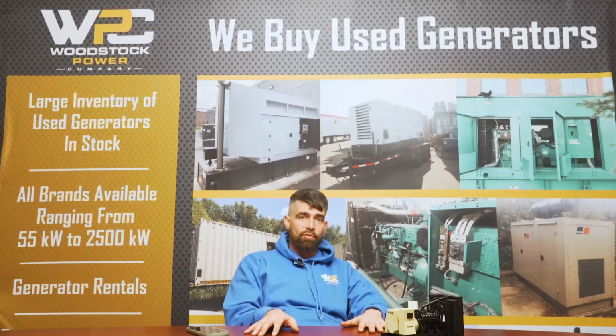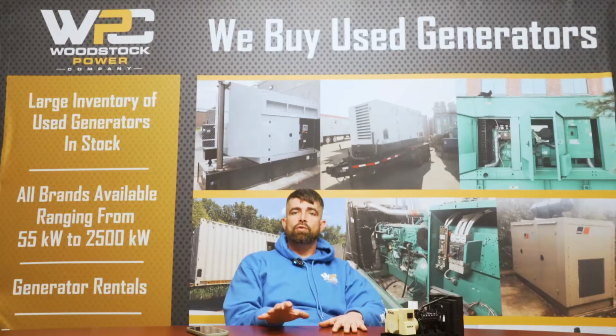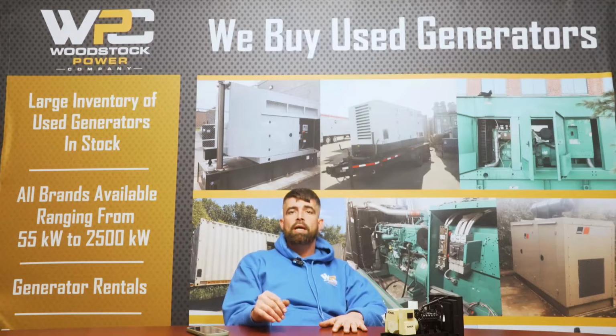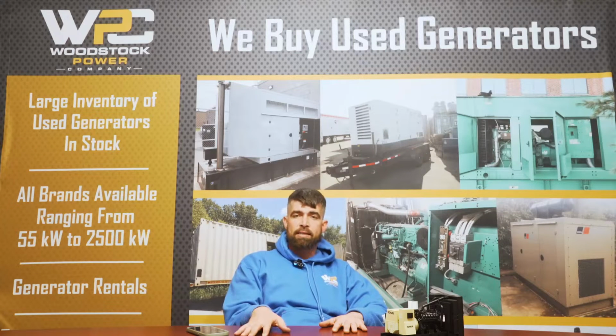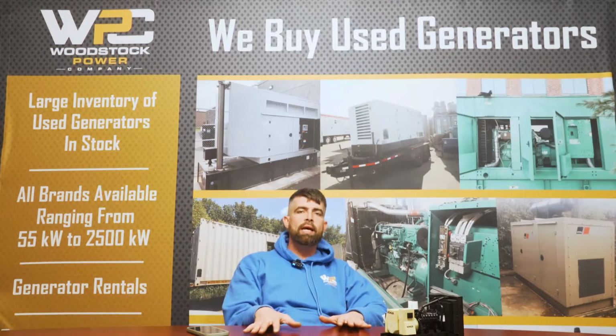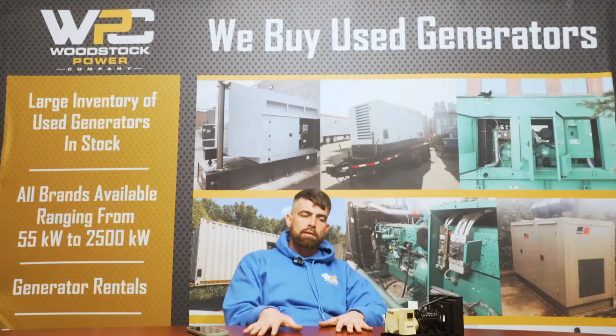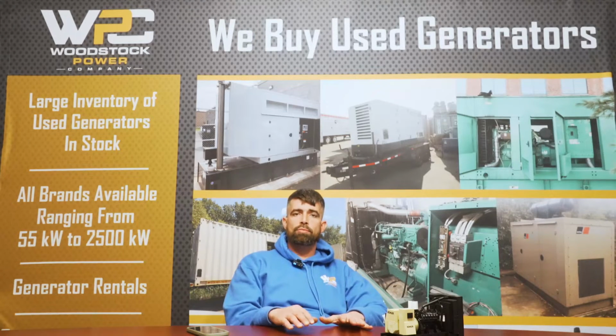Every time after you do an oil change, or after you get a service done on your machine, make sure that you clean all the spillage, make sure that you clean anything that went over, any items that might have been forgotten, any rags, any papers, anything like that that does not belong in there. That is almost always a cause of problems with generators.